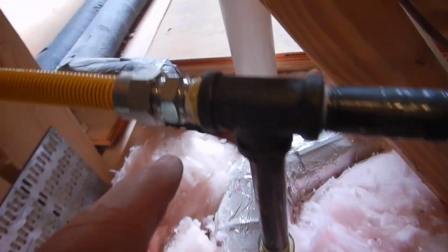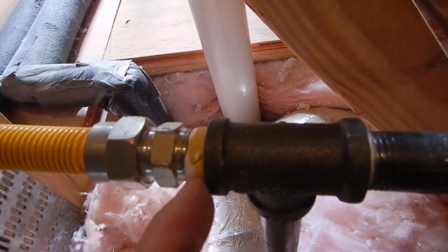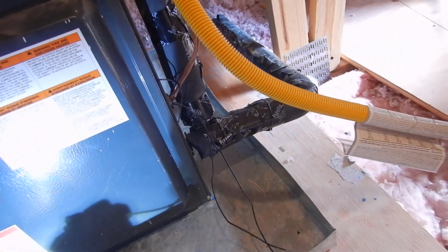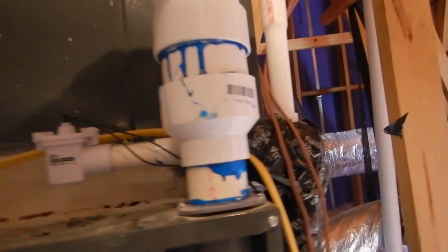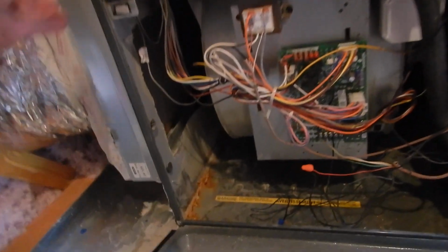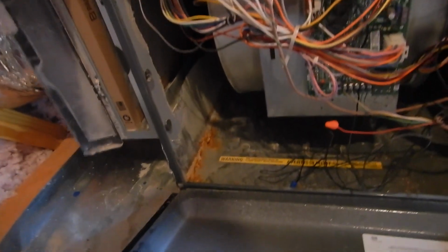I'll do some homework. Coming on up, so that's our furnace, gas pipe, sediment trap, yellow tape. Nope, that's white tape. White tape on this one too. Okay. Well, come on, guys. You can do better than that. Evaporator coil, we do not have a P-trap. And then on our air filters, our air filter is a 20 by 25 by 1.